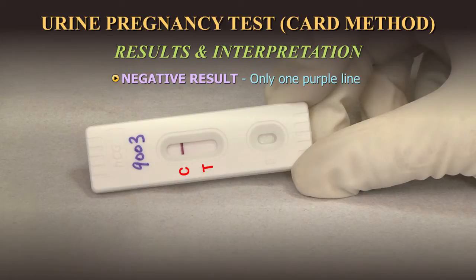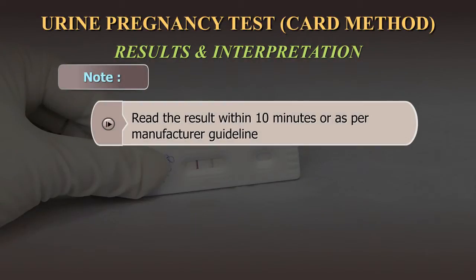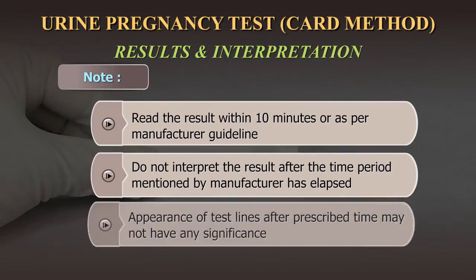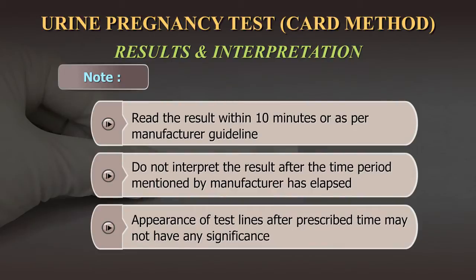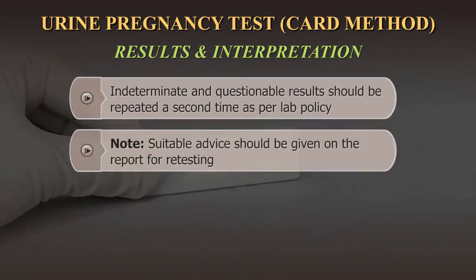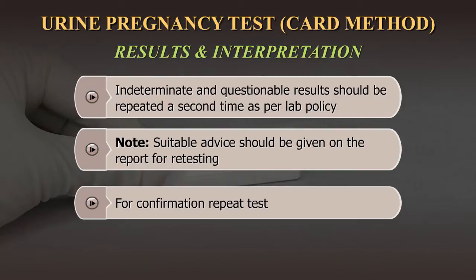A negative result is indicated if only one purple line appears in the result window at C. If no lines appear in the result window with distinct colour, it is an invalid result and it is recommended to repeat the test. Read the result within 10 minutes or as indicated by the manufacturer. Do not interpret the result after the time indicated, as appearance of test results after this time may not have any significance. Results are reported as either positive or negative. Questionable results should be repeated; discard the used test device and repeat with a fresh device and fresh sample.